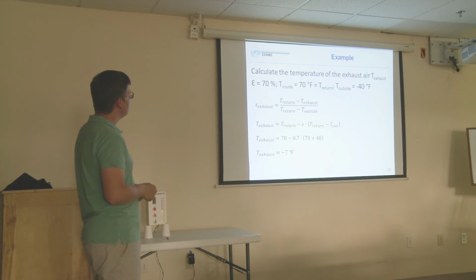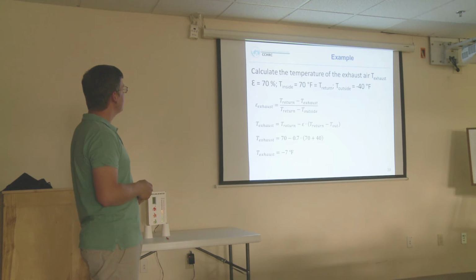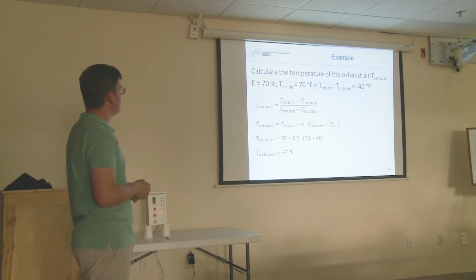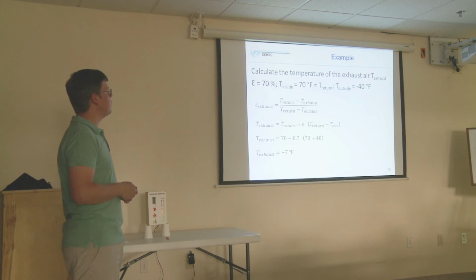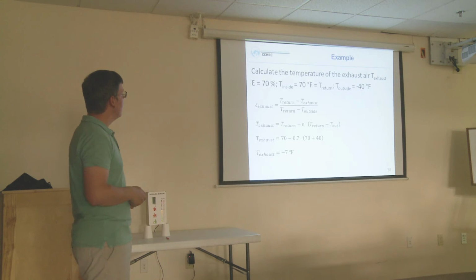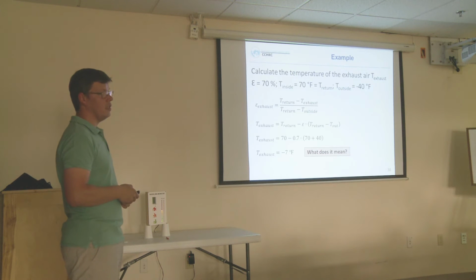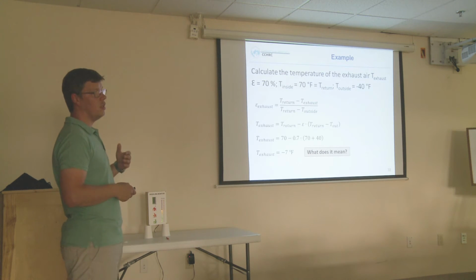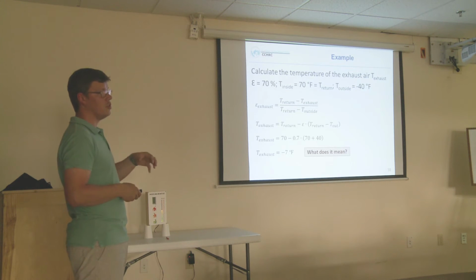And there is a little example. Assume we have a 70% efficiency or effectiveness of the heat exchanger, and an inside temperature of 70 degrees Fahrenheit, that is our return temperature, the air that goes out. And then we have an outside temperature of minus 40. Then we can calculate how cold the air which goes out of the house will be after it was cooled down. We do the math, and we end up with minus 7 Fahrenheit. That's quite cold air. And what does that mean? If that air from inside the house is cooled to that temperature, there is a lot of moisture in that air.